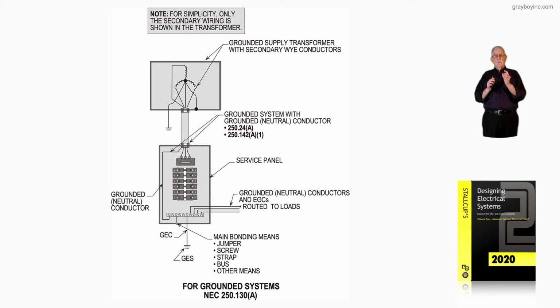Now, to close this illustration out, the grounded conductor from the secondary side of that transformer to the main has to be routed with the phase conductors. The equipment grounds that you see have to be routed with the phase conductors. And if you have a neutral and an equipment ground, both of them have to be routed with the phase conductors, is the basic rule. And then the main bonding jumper that you see in the illustration could be a conductor jumper, could be a screw, could be a strap, could be a bus, or other effective means that would be approved by the authority having jurisdiction. Now that's what this Figure 16-116 is illustrating for grounded systems in accordance with 250.130A.